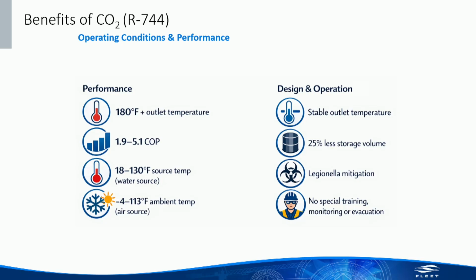Another benefit of CO2: all heat pumps increase or decrease their output depending on source temperatures - the warmer they are, the more output you get, the lower the source temperatures, the less output. However, with many refrigerants the outlet temperature will also decline as source temperatures lower. With CO2, we're able to maintain a consistent outlet temperature regardless of source conditions, so we can always design for that 180 degree outlet water no matter the source temperature, which helps when designing the storage elements of the overall system.